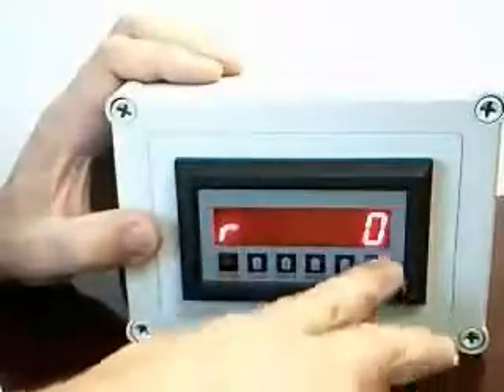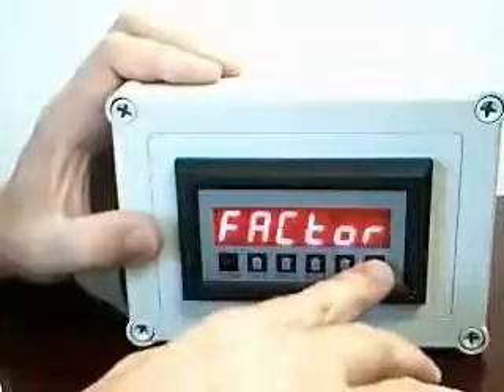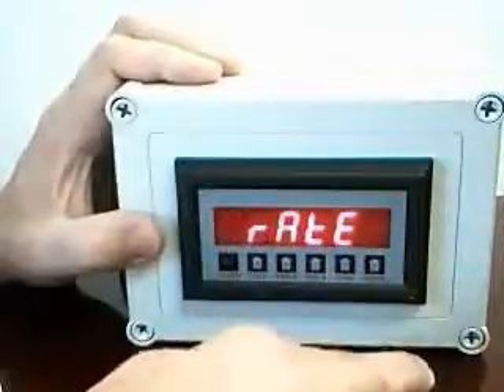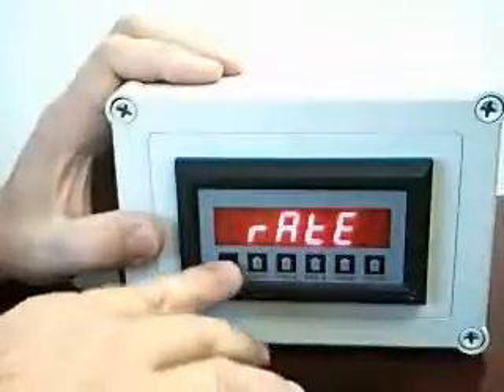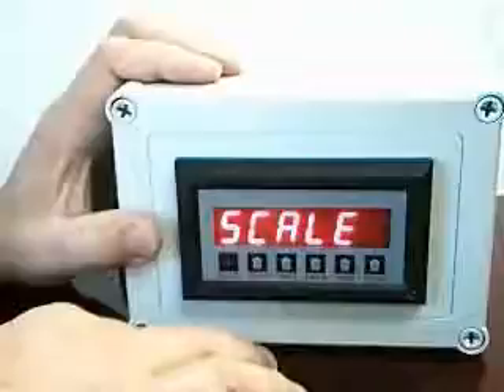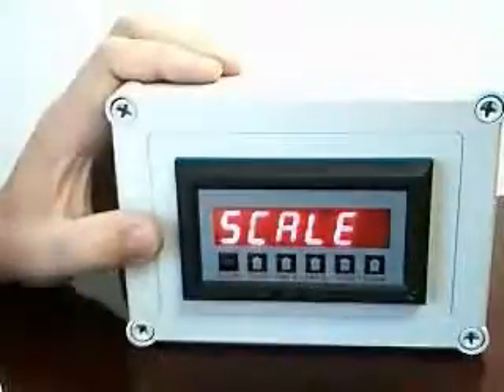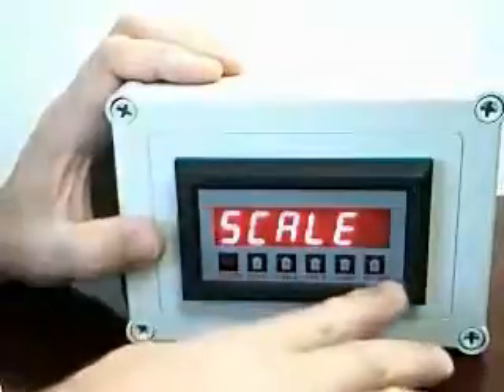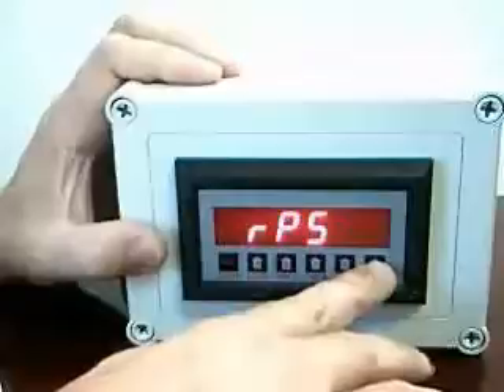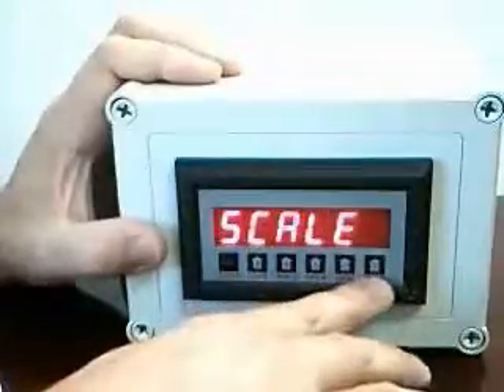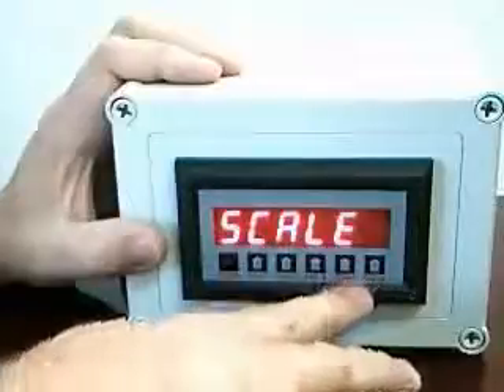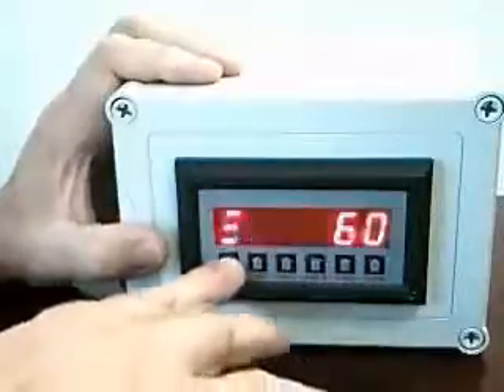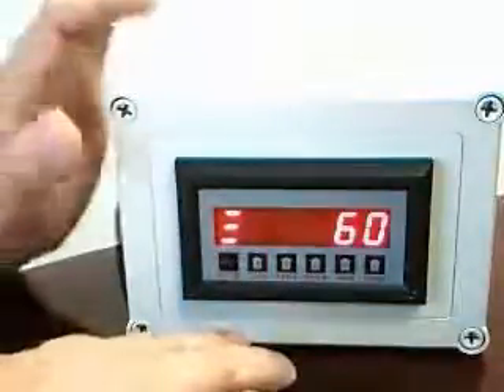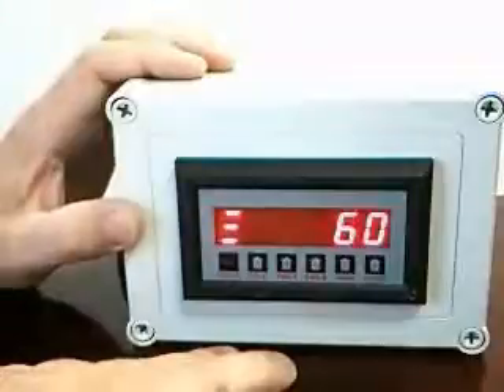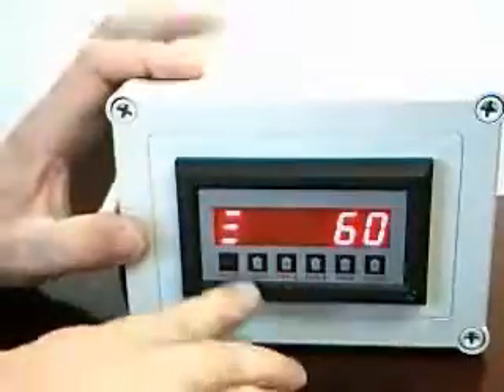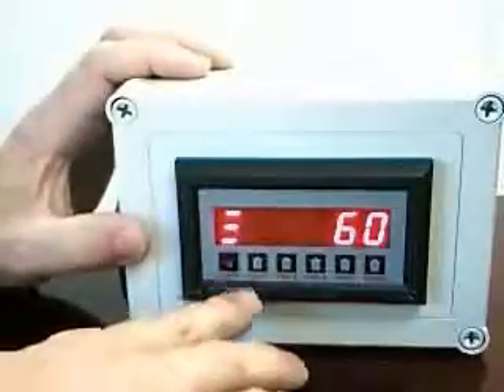Let's go to the next menu group, which is associated with the rate. Pressing the program button several times brings us to the rate submenu group. Pressing Enter brings us into that menu. Now the first menu has a selection on it that lets me either display the rate in rate per second or select scale, where the instrument will permit me to choose a scaling constant. I'm going to hit Enter with scale, and this symbol with the 60 indicates that I want to read in rate per minute. That's the selection we wish to use on this application, so I'm going to hit Enter.